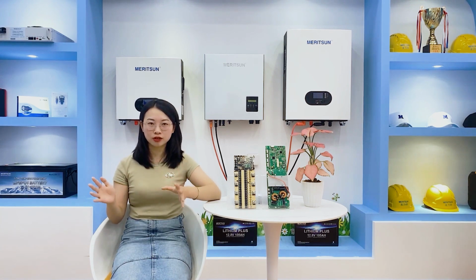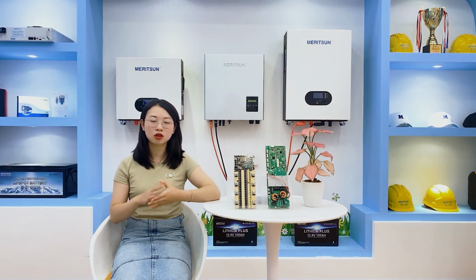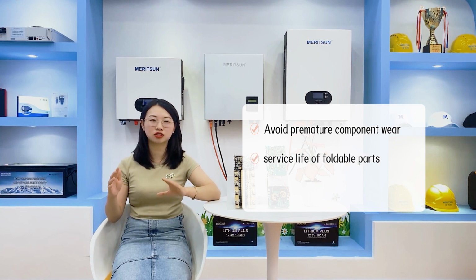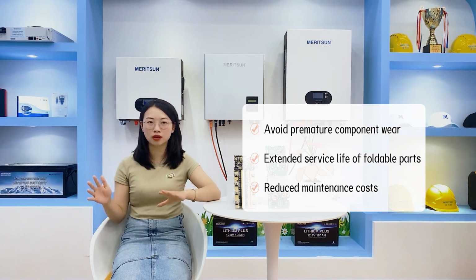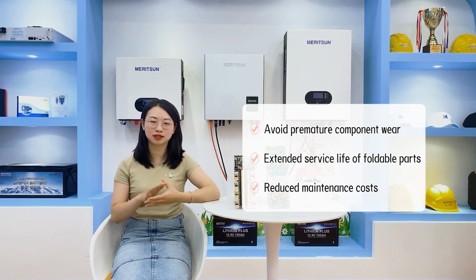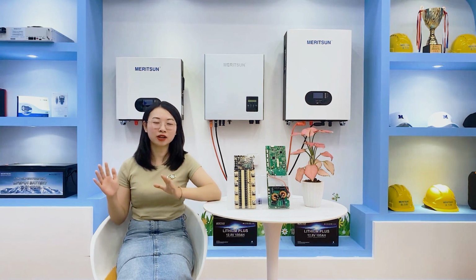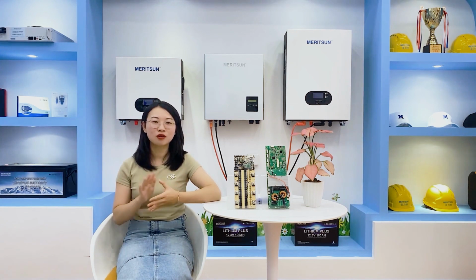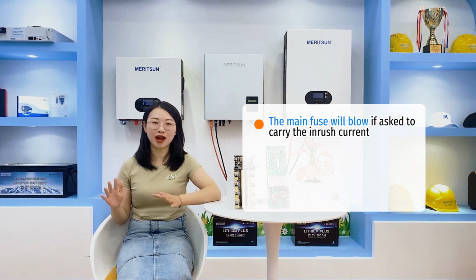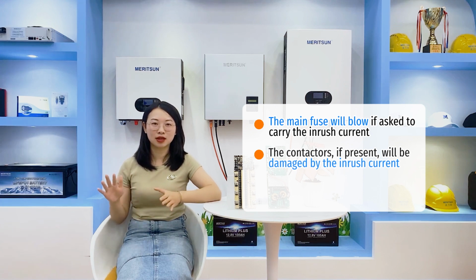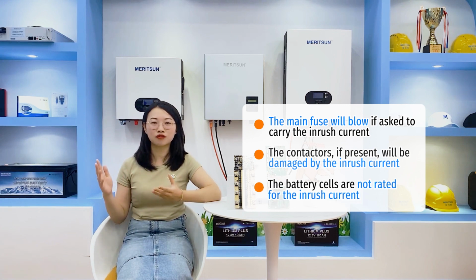With the pre-charge function of the battery BMS, it allows safe use of a wider range of inverters with different input requirements, helping to protect the inverter and other connected components from premature wear. This extends the life of equipment and can reduce maintenance cost. Besides, the pre-charge function can also avoid the following issues. First, the main fuse will blow if asked to carry the inrush current. Second, the contactors, if present, will be damaged by the inrush current. Third, the battery cells are not rated for the inrush current.